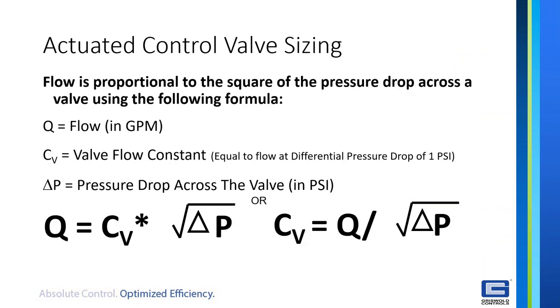Now we want to talk about control valve sizing. And the actuation, we had to do that first because the control valve sizing does come into play when you are trying to size a valve. But I'm just going to talk about control valve sizing. First off, we're going to do it the longer way with the formula, so it makes sense to you. But don't worry, we will, in the end, give you a simpler way and then an even simpler way with our pressure-independent valve. We just want to look at the basic formula here for selecting control valves, because it's good to understand what's behind all of the computer programs and all of the rules of thumb and everything.